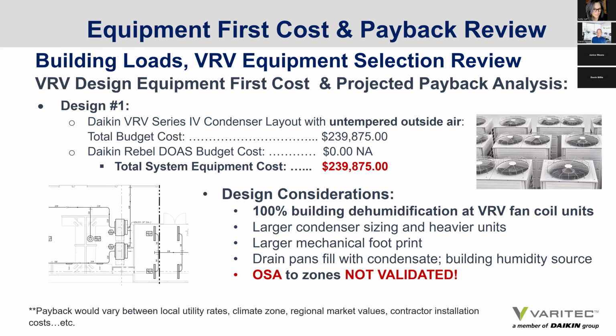Design considerations. 100% building dehumidification occurs at the VRV fan coil units. Larger condenser sizing, larger, heavier units, larger mechanical footprints, drain pans filled with condensate, outside air to zones not validated. How do you know that each fan coil is drawing the appropriate amount of outside air to each zone when you're leaving it to a negative pressure component in the return air outside air system?